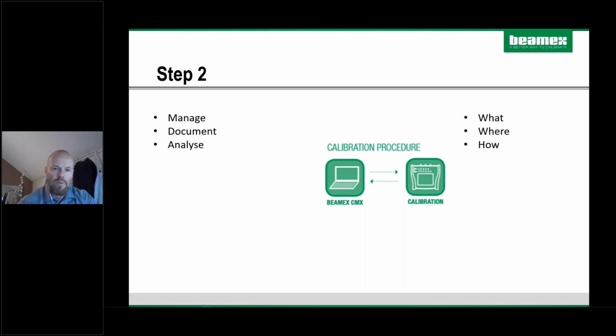So the calibrator is documenting your job in the background, and all the data is in the calibrator, but it's a small calibrator that you can drop, from 5 meters up on a ladder or something like that. So it's normally only a temporary storage, but when you upload it to a computer with large screens and keyboards and everything, you can analyze and make all kinds of reports, do history trending, see error calculations and pass or fail results, and even print certificates and look at the data. Everything is documented for you there.